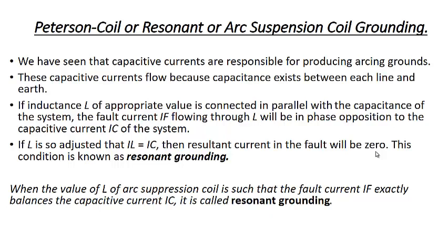So in this case, with the Peterson coil or resonant coil, the resultant current has been made equal to 0. That is why this condition is known as resonant grounding. When the value of L of the arc suppression coil is such that the fault current IL exactly balances the capacitive current, it is called resonant grounding.